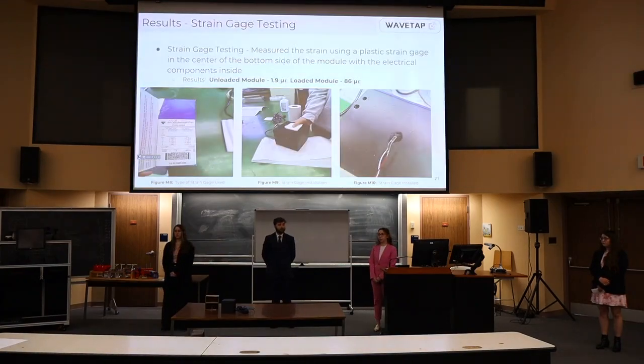We also did some strain gauge testing to make sure that the weights of the electrical components did not cause any issues on the housing. We had the module tested without the transformer in it and then with the transformer in it. The results that we got with the transformer being put back on it was a load module value of about 86 microstrain, which again is very small and should not cause any issues or any deformations.